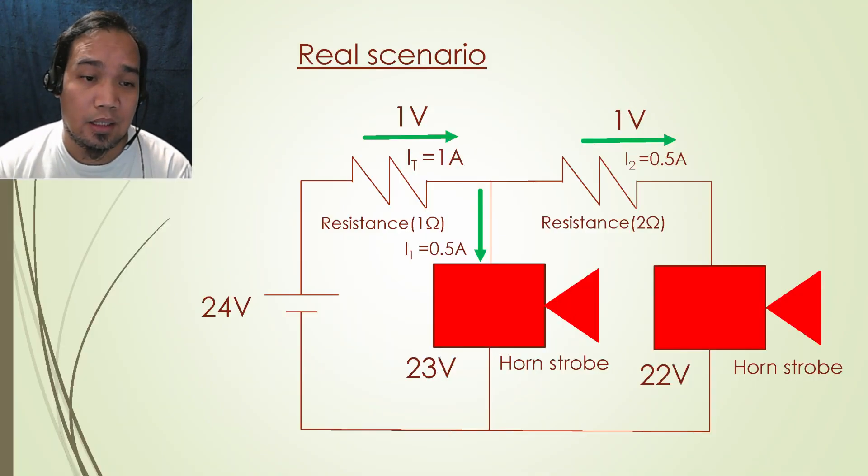Now here is another real scenario from the fire alarm installation. In this illustration there are two number of horn strobe connected from the voltage source. To calculate for the voltage drop, the type of the circuit to be considered is series-parallel. Horn strobes are connected mainly in parallel while the cable resistance is in series prior to the device.